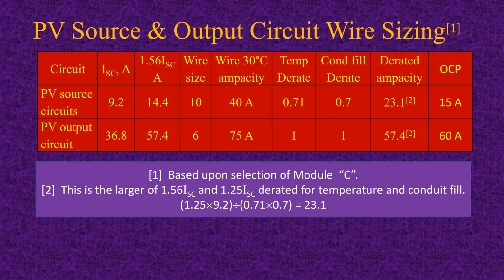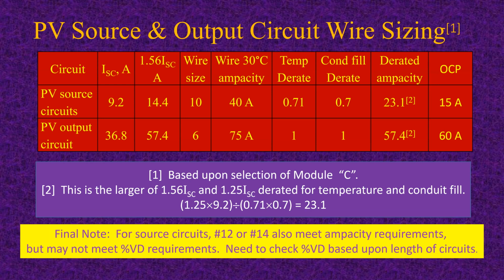And this wire size, but in the output circuit where you've got almost 60 amps, then you're probably going to use number 6 wire. Okay, that's where you've connected all of your source circuits together to have a single output. Okay, and number 12 and number 14 wire meet the ampacity requirements. So the only thing you need to be concerned about is whether they meet voltage drop requirements.